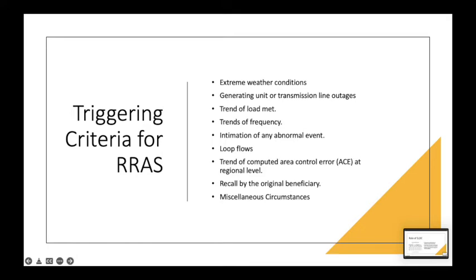Now the RLDC, by 1800 hours, that is by 6 pm, will publish the schedule for all the interstate generating stations for 29th of June from 00 hours till 2400 hours. That 1800 hours schedule, which has been first prepared by the RLDC keeping in mind the demand and supply scenario, is called revision 0. Once this revision 0 is published, any subsequent change will be called revision 1, revision 2 or any other revision number.